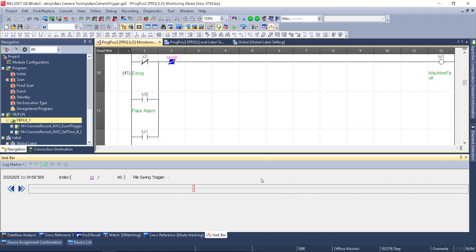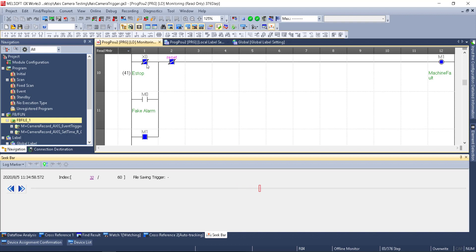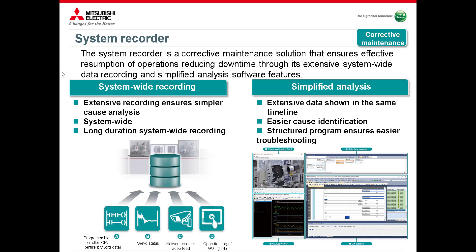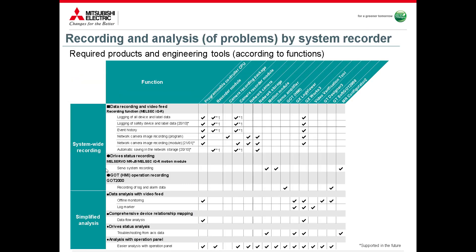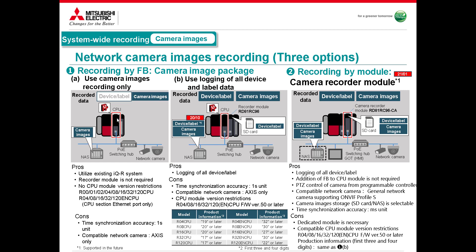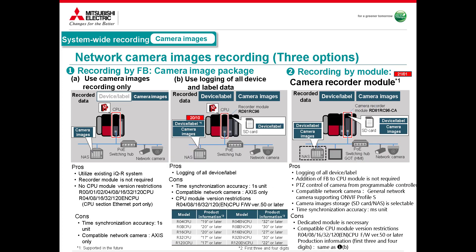If you had an equipment problem — something jammed, a proximity switch or a dog didn't make, the product was incorrect going down the line — you can see that exact moment in time. In GX Works 3 I stop the current offline monitor session and then select the new logging file we just created. We jump right to the point where M1 turned on. As we move through frames one at a time, we can see the E-stop came on and M1 came on. That summarizes system-wide recording and simplified analysis — step 1A. You can test this now with an off-the-shelf CPU and an Axis camera. Thank you for your time — I look forward to showing you steps 1B and step 2 in the near future.